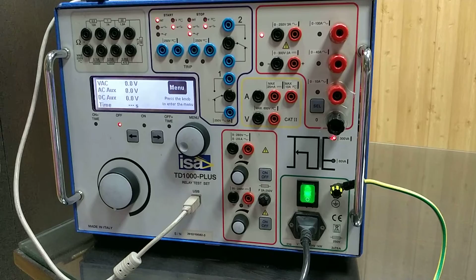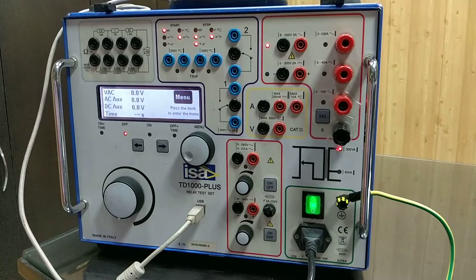In some applications, like very low current or earth fault related tests, we need a very precise current. To generate that precise current, we can use these resistance sections which provide additional smoothness of current variation.